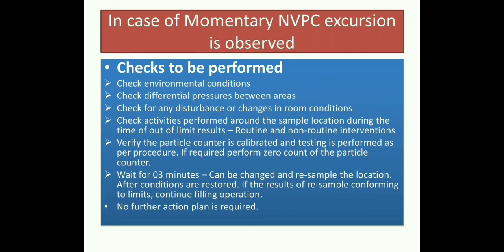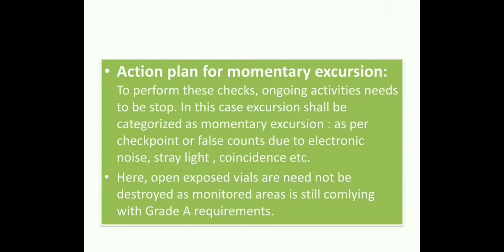In such cases of NVPC excursion, we should wait for three minutes — this three-minute criteria can vary with the organization or design of the area. We then wait for room conditions to be restored, and once restored we perform resampling at that location. After resampling, if the area is confirming to its classification — mostly Grade A for injectable filling — and complying with Grade A requirements, no further action on the routine or ongoing filling activity is required.